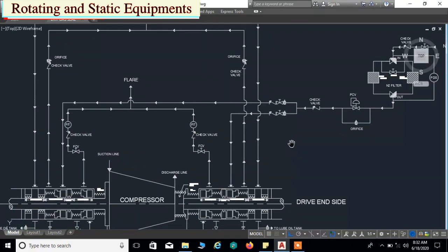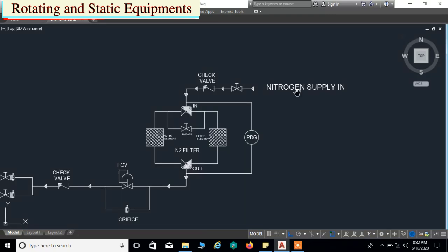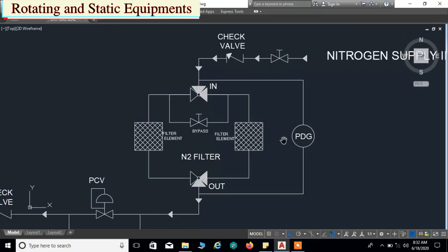Next we will go to the nitrogen gas injection supply. The inlet pressure of the nitrogen gas is 8 bar. The nitrogen gas passes through a filter for removal of foreign particles and dust. This is a replaceable cartridge type twin gas filter, piped in a parallel arrangement using a continuous flow transfer valve. Normally one filter is online and the other is on standby. If the filter differential pressure gets high, the working filter is choked and an alarm is shown from the DCS. We then change over the filter, and the filter element filtering size is 2 to 5 microns.